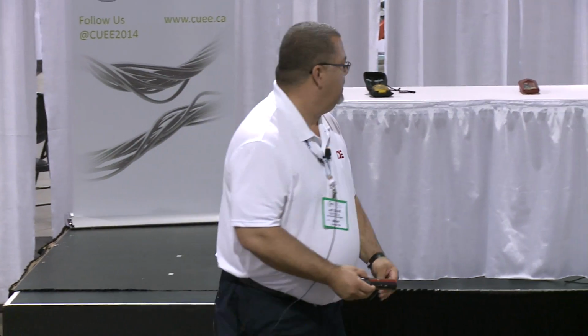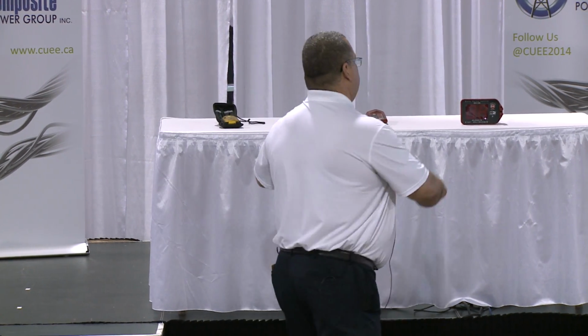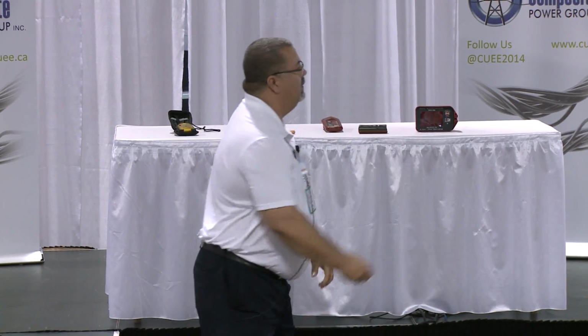So we have to use alternate methods back at the connection points to determine whether a cable is energized or not on our primary cable. It will, however, the devices we talk about will measure the electric field around a cable like this. Field strength is proportional to voltage and distance.